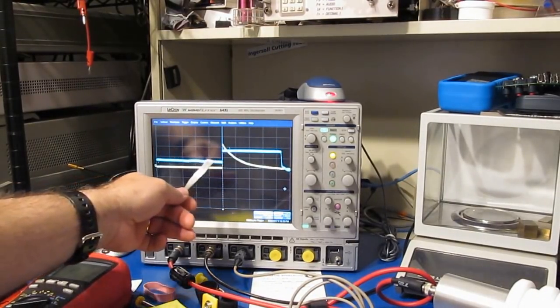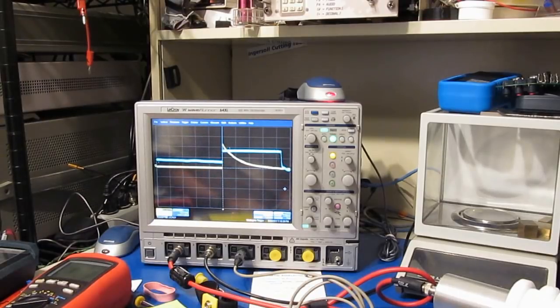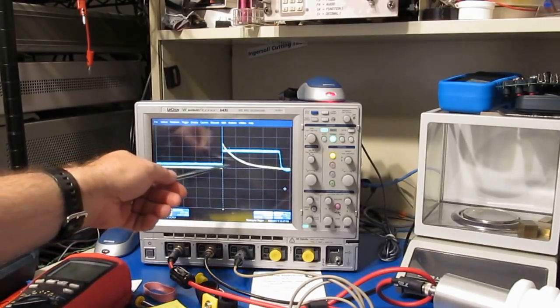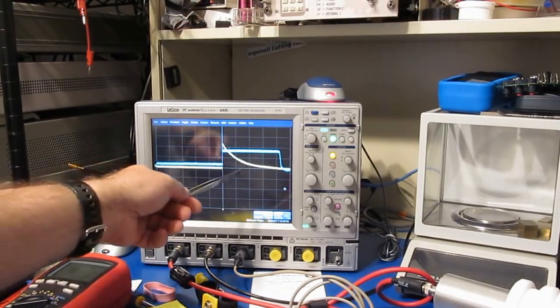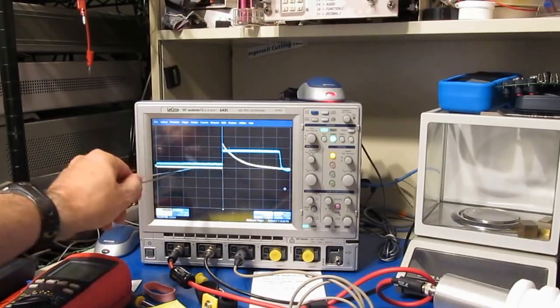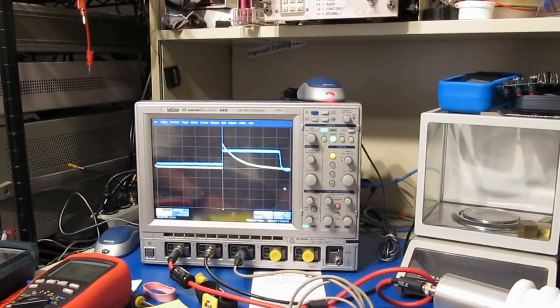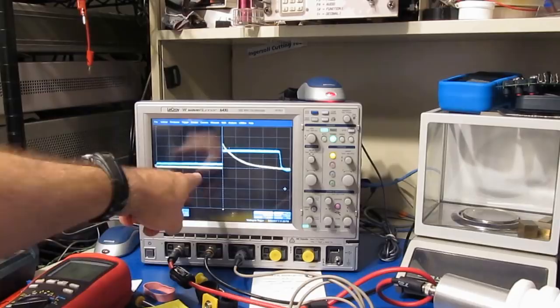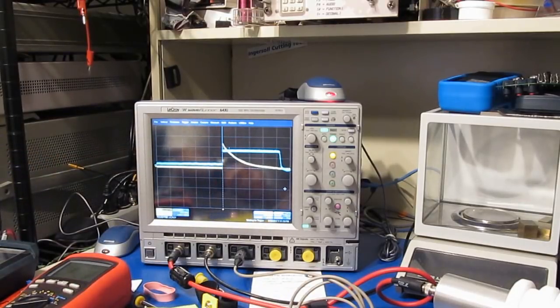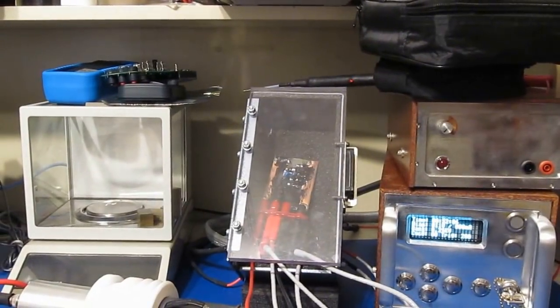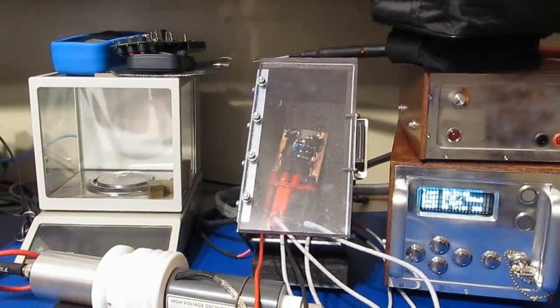The reason you see the baseline moving around is I have a transformer inside the transient generator to output 220 volts AC, driven off a solid state relay. It has enough leakage current that I'll always get some residual AC voltage riding on this. You'll never see the blue line fall below ground because the output of that transformer goes through a bridge rectifier. So these two parts look pretty good.